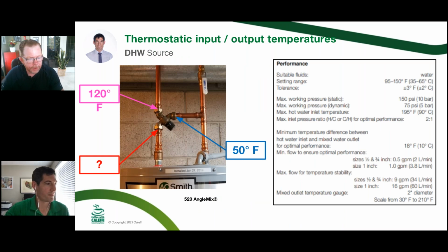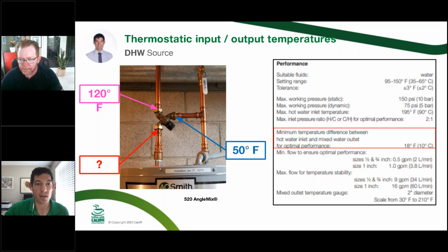Input and output temperatures. Let's talk a little bit about this, Max, from the standpoint of our domestic hot water source. Okay, so as Cody Mack, Caleffi, one of the other trainers, says, the mixing valve does not add heat to the system. So if you need 120 out, you cannot set that water heater for a 120 set point. It will not be able to mix with anything and maintain 120 out. So in this case, you would need to add 18 degrees to that, and that's going to be your set point for the water heater.